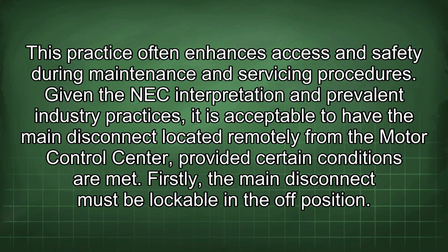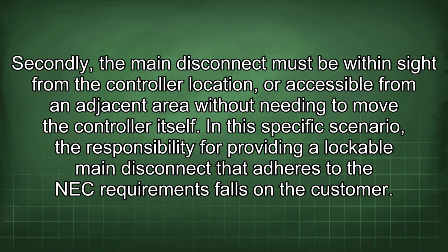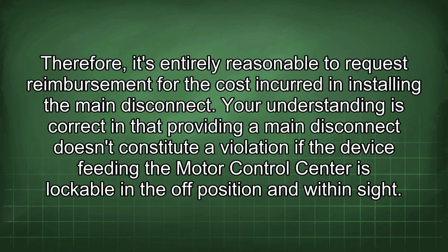Firstly, the main disconnect must be lockable in the off position. Secondly, the main disconnect must be within sight from the controller location or accessible from an adjacent area without needing to move the controller itself. In this specific scenario, the responsibility for providing a lockable main disconnect that adheres to the NEC requirements falls on the customer. Therefore, it's entirely reasonable to request reimbursement for the cost incurred in installing the main disconnect.